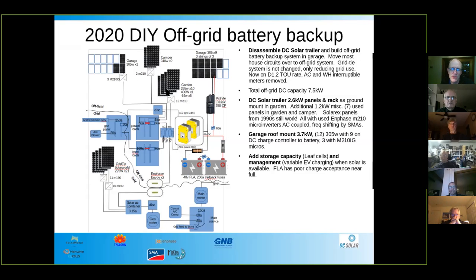So the panels in the upper left are all AC coupled, and they come down either back into the loads panel directly in the garage, or the ones in the garden come through conduit all the way over into this other small distribution box, which is the main output of the Sunny Island inverters.